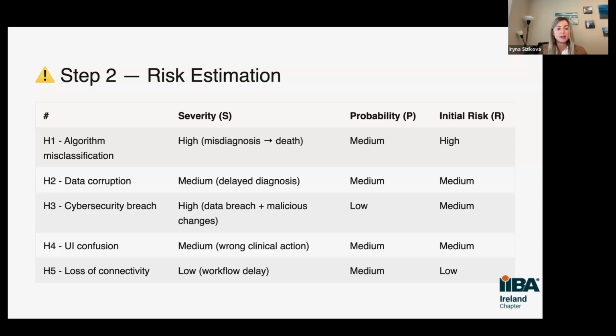Hazard number 3 is cybersecurity breach. Severity is high, because it can mean changes to our data or a data breach, and we violate a law. Consequences could be quite serious, even financial penalties for a company. Probability is quite low, and multiplying high by low, we get a medium initial risk. Hazard number 4, UI confusion: we have medium severity because of wrong clinical action, and medium probability. What is the probability this risk could happen? As a result, we get a medium initial risk.